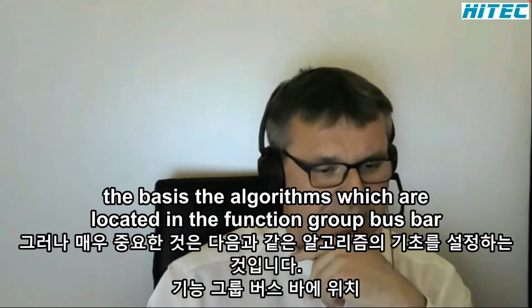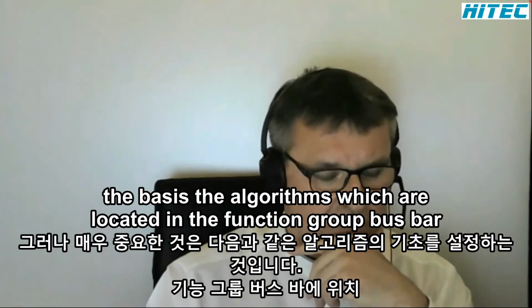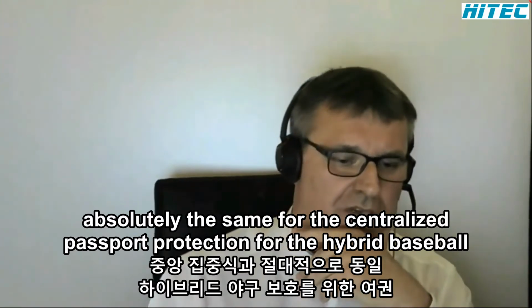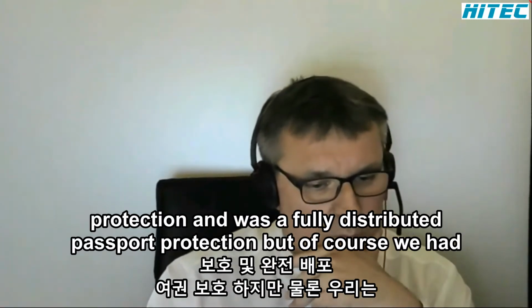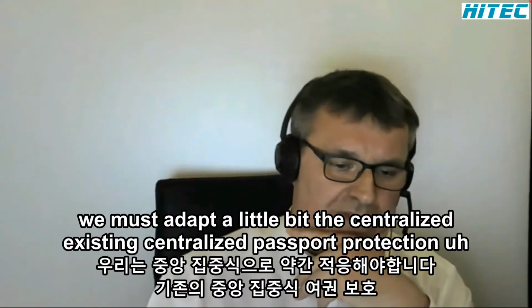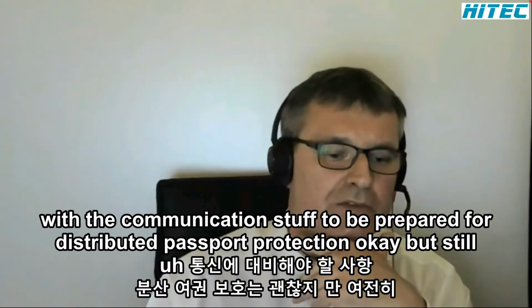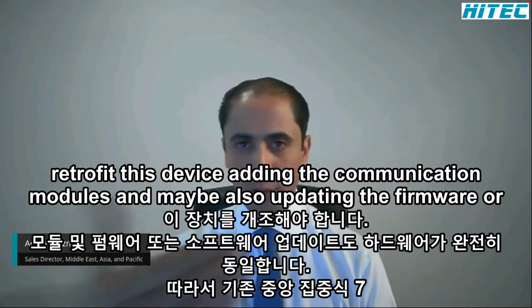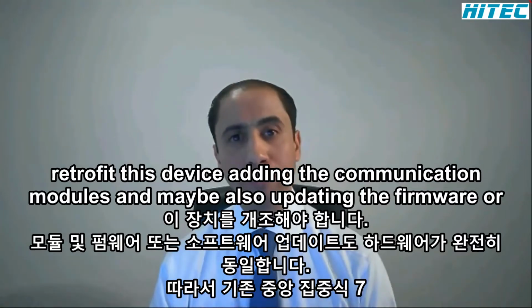But what is very important is to state that the basis, the algorithms which are located in the function group busbar, are absolutely the same for the centralized busbar protection, for the hybrid busbar protection, and for the fully distributed busbar protection. But of course, we must adapt the existing centralized busbar protection a little bit with the communication stuff to be prepared for distributed busbar protection. Still, we can use the same hardware. We just have to do some adaptations. We have to retrofit this device, add in the communication modules, and maybe also update the firmware or the software. The hardware is completely identical.